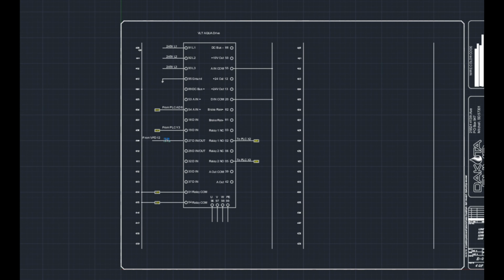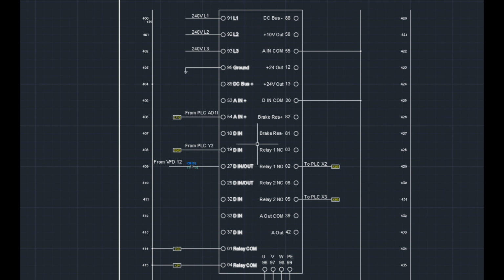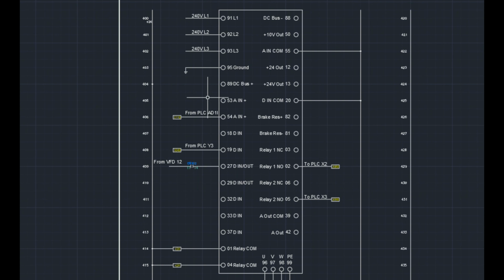And this is my VFD. The only thing that changed in this was the 54 analog in. We had to use 53 because of some issues with the drive, but we switched it over to 53, and I will show you that real quick.